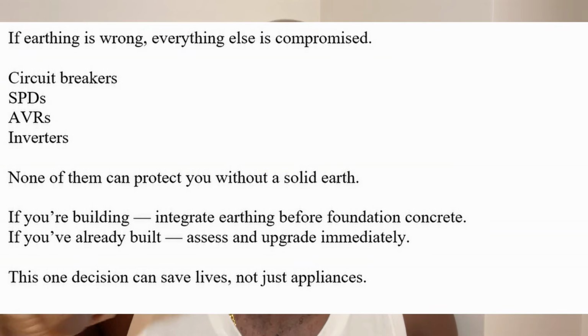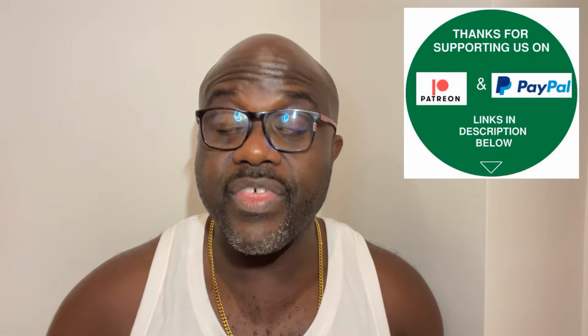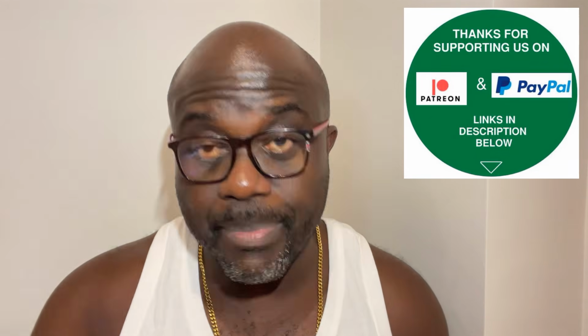What I'll say finally about earthing: if earthing is wrong, everything else is compromised. The circuit breakers, the surge protective devices, the automatic voltage regulators, AVR, the inverters, none of them can protect you without a solid earth. The earth is the reference. The earth is the safety reference. Okay? If you're building, integrate earthing before the foundation concrete is poured. If you've already built, no problems, assess the situation and upgrade immediately. This one decision can save lives, not just appliances.